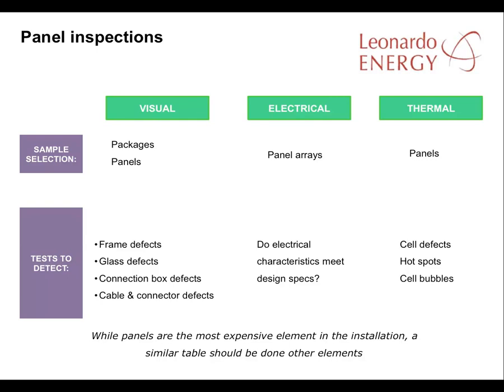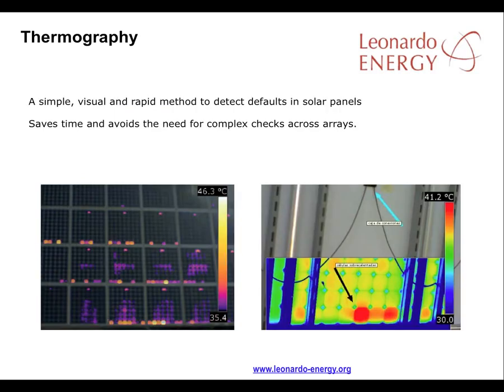The electrical inspection tests whether the panel array's characteristics differ from the technical specifications used for the design, while the thermal inspection of panels searches for cell defects, hot spots, or cell bubbles. Thermal inspection of the modules is a simple method to detect faults in the solar panels. The check is a rapid and visual one using a special kind of camera that highlights thermal hot spots in the panels which might indicate a defect. The picture on the right shows you what defects might look like, with the affected cells highlighted in red.